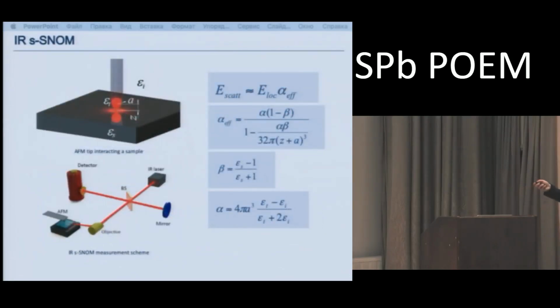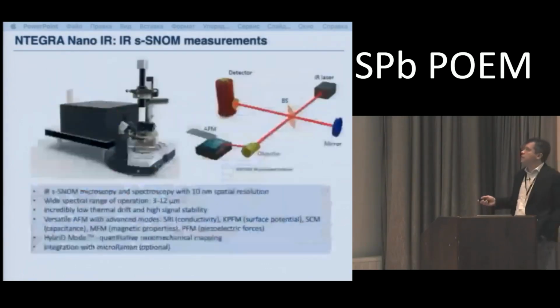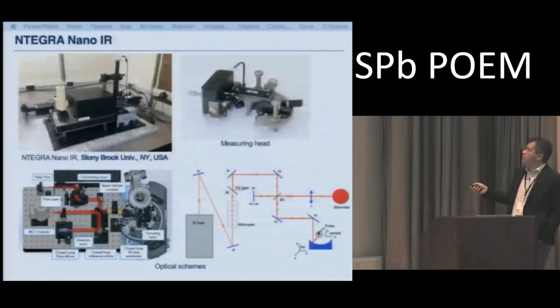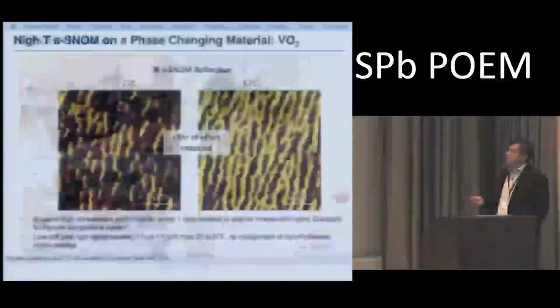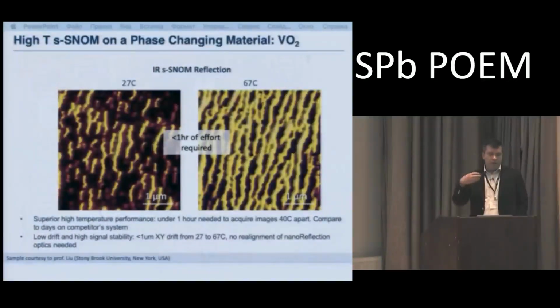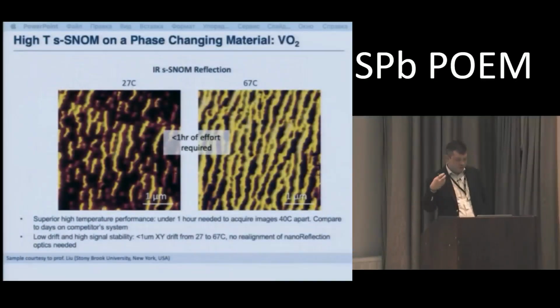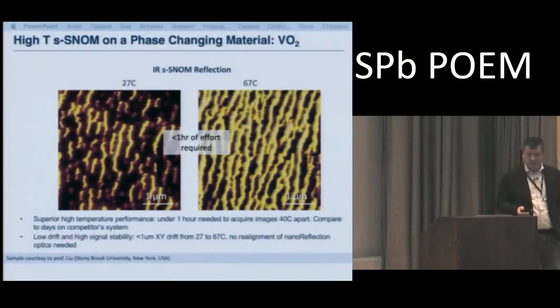The dependence of the scattered field on the distance between the probe and the sample is strongly nonlinear. So at the doubled or tripled frequency of the cantilever oscillation, there is an optical response that refers to the complex dielectric permittivity of the sample. After amplification with the optical interferometer, this signal is analyzed, and we can measure the optical amplitude, optical topography and optical phase of the scattered light.